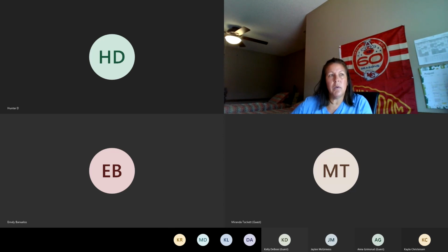In our units, that would be referring to making sure that in the room that's closest to your locker room, on that one, you have to make sure you select the little computer. There's a piece of film and a computer, and you want to make sure that it's on digital, which means you want that little light to light up by the computer. And then we always want to make sure that we're selecting adult or child. Child drops it almost by half. So we want to make sure we're not using an adult exposure on a kiddo.